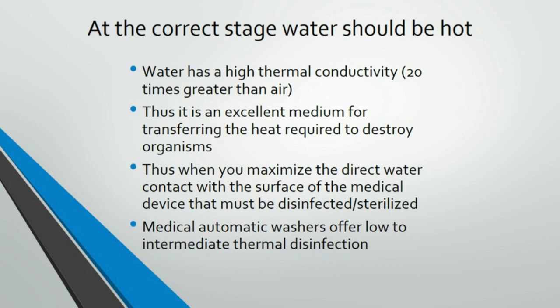That's what you want. Medical automated washers offer low to intermediate thermal disinfection. So we say thermal disinfection, but we're not saying high level. That's just a qualification there. Thermal disinfection isn't high level disinfection. It's considered low to intermediate.